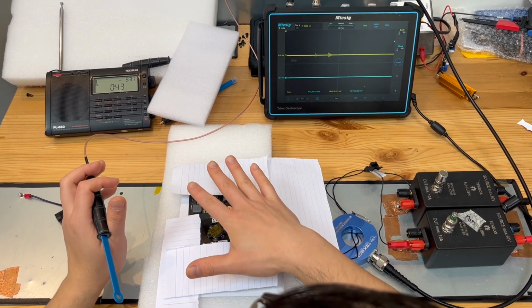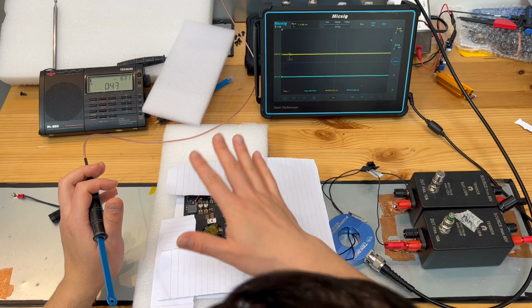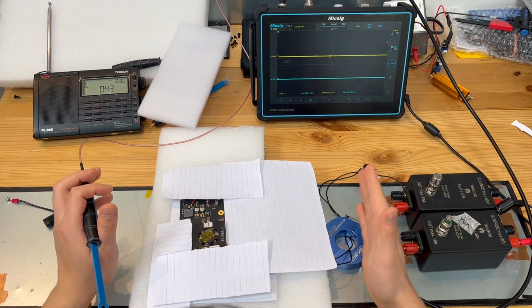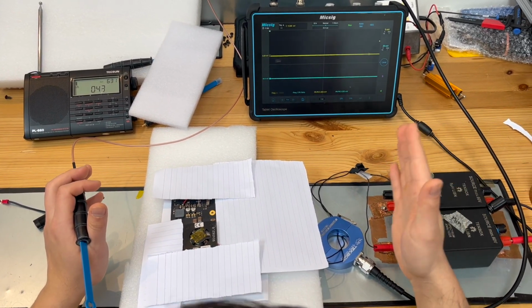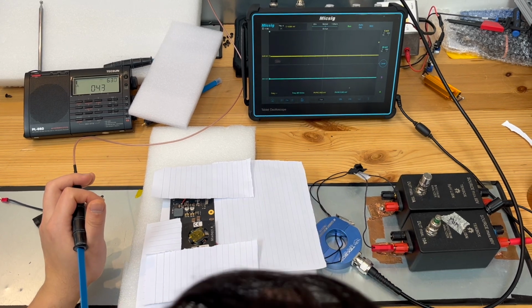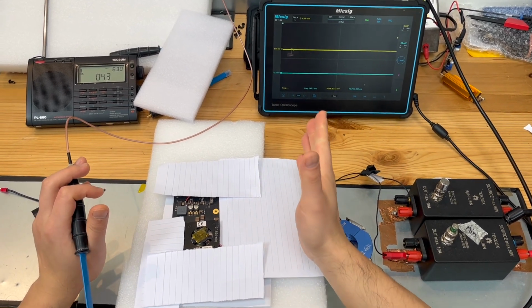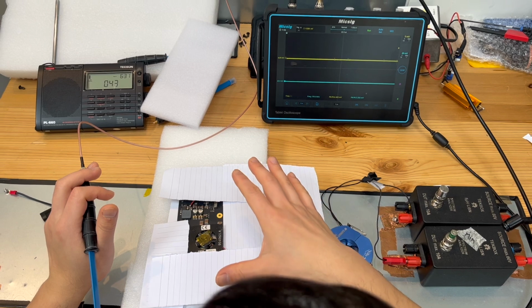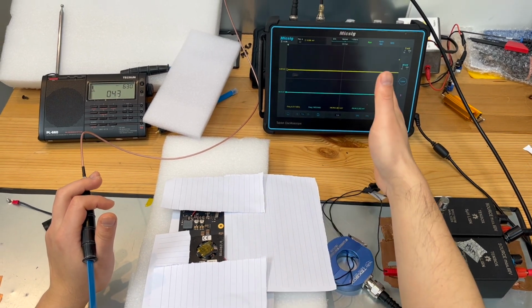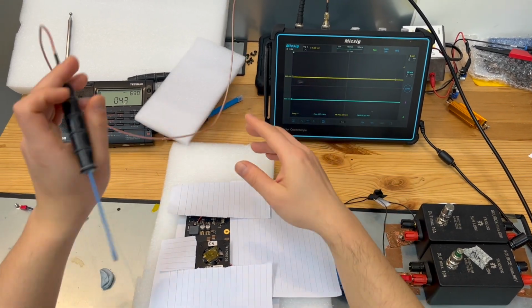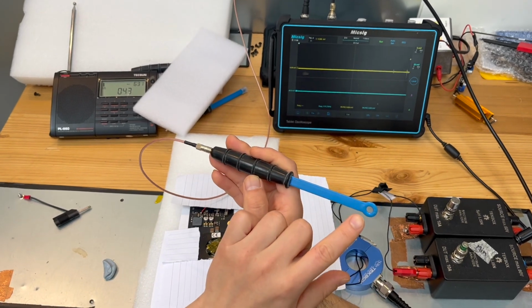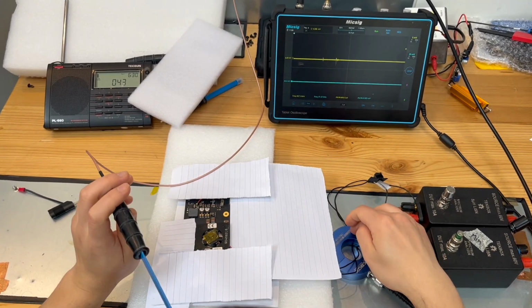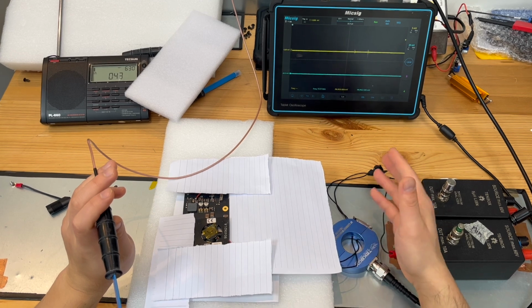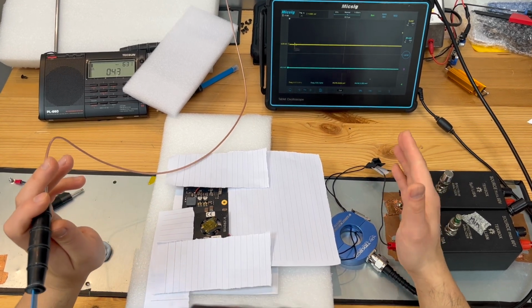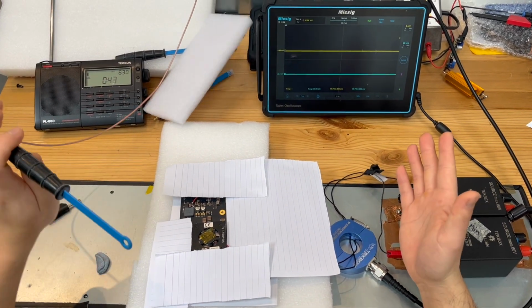3 or 5 or 7 noise sources. And you wonder which noise source contributes to the particular noise that we are trying to deal with in the conducted emission. And this technique enables you to trace and track the noise because it's in the time domain. So you can compare whatever you measure using the small field loop to the waveform you measured with the RF current probe, so that you know which noise source contributes to which content, okay?